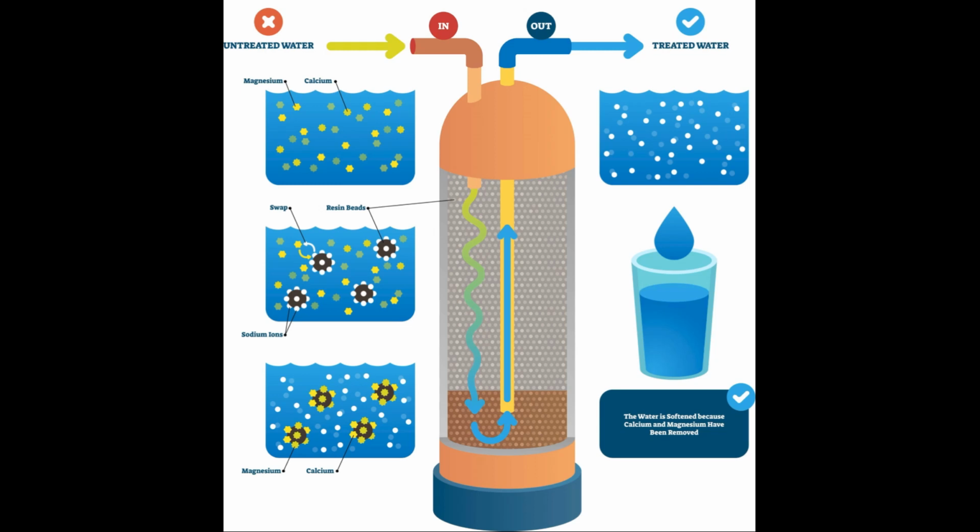Knowing the total hardness of the water being treated is very important. The calcium and other heavy metals remain on the softener resin bead until they are regenerated by passing high dosages of salt across the resin bead to push off the heavy metals and replace them on the resin. This is the softener regeneration process. The frequency of the regeneration process is based on the amount of total hardness in the water being treated.